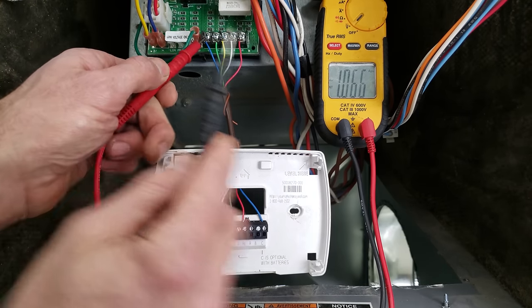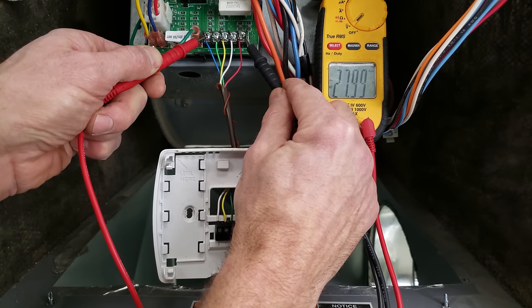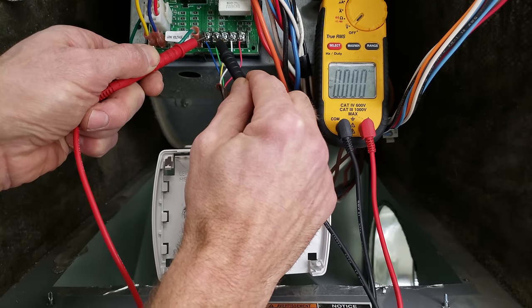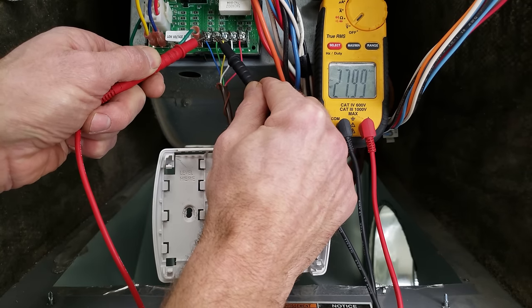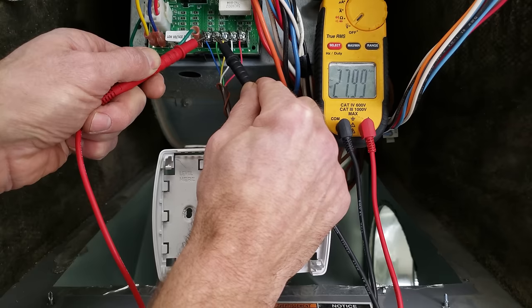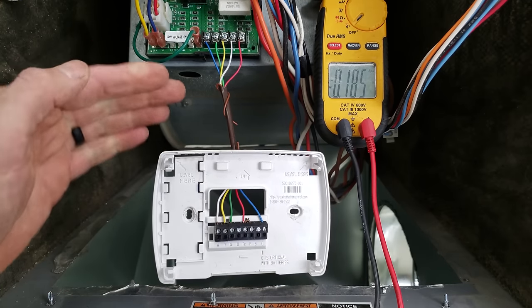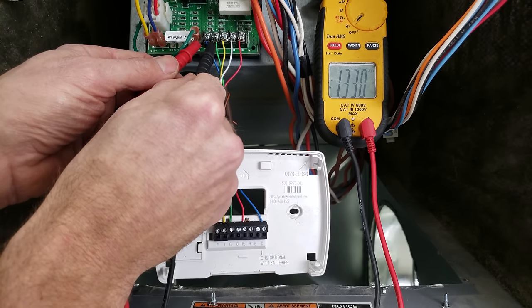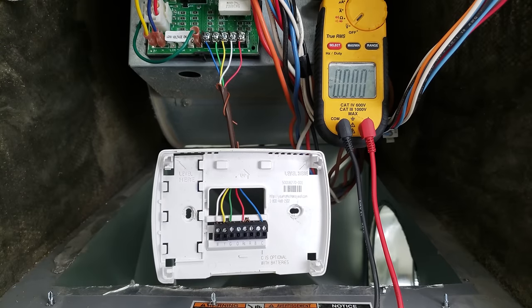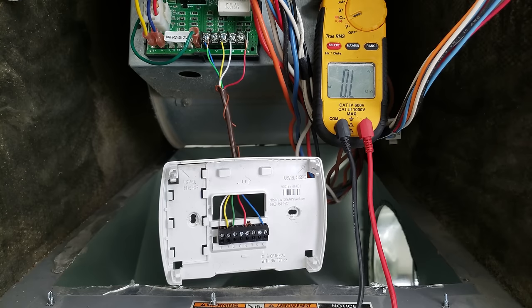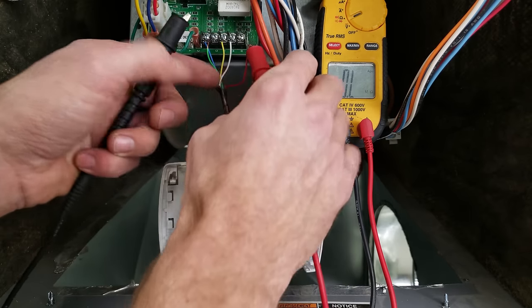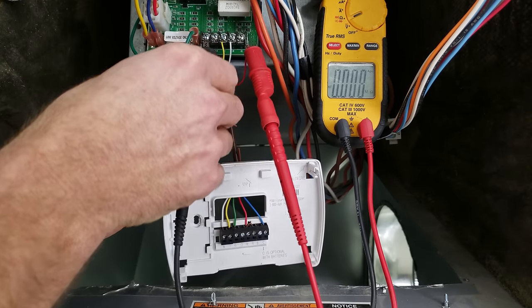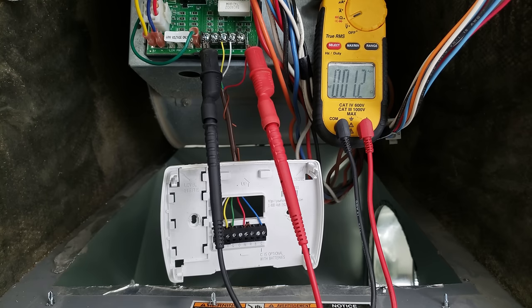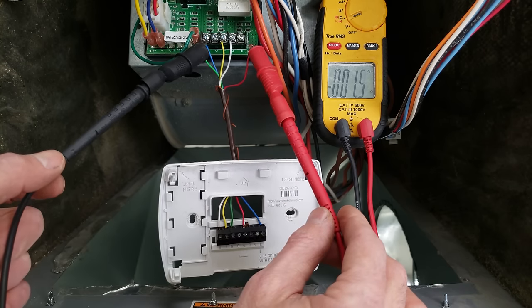So what we do right here is we should always have from common to R 24 volts. So we got 28 volts right there, and we should have 0 volts right now from G to C, but we actually have 28 volts. And that's due to this thermostat wire, because there's nothing else that would be connecting this G wire to the R. So what we're gonna do is turn the power off to this furnace. So now we can check electrical resistance between the R and the G, and we should have no electrical resistance. In this case though, you see we have 1.2 ohms, so those two wires are connected.